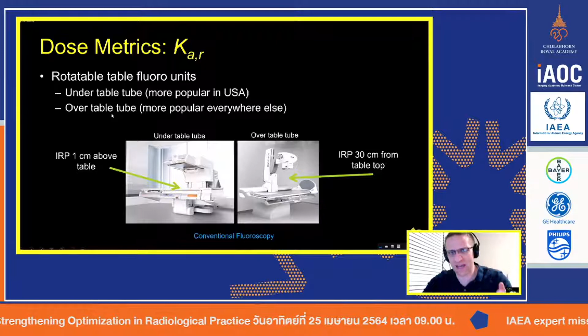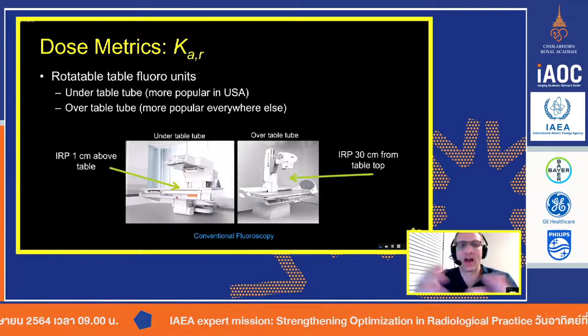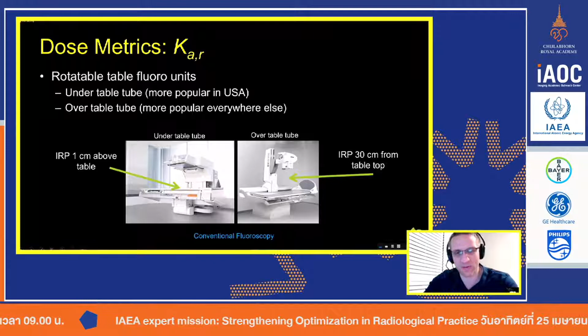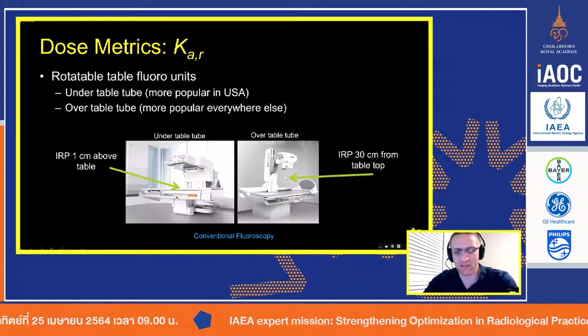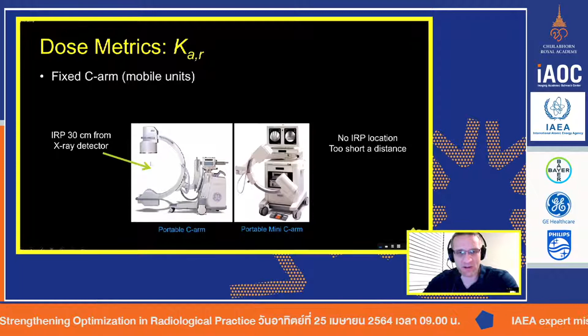So as I mentioned, every type of fluoroscopic system has an international reference point at a different location. You and I know fluoroscopy comes in a variety of different geometries, different flavors. You have your typical C-arm for your interventional systems, your cardiac cath labs. For routine conventional fluoroscopy performed in radiology, you'll have either an under-table X-ray tube or an over-the-table X-ray tube. In the case where it's under-table, the international reference point is 1 centimeter above the table. In the case of an over-table tube, the value is 30 centimeters above the tabletop. So here you see it's slightly different. In a fixed C-arm, typically found on your mobile units, it is 30 centimeters from the detector.